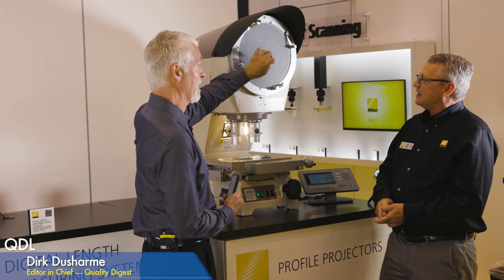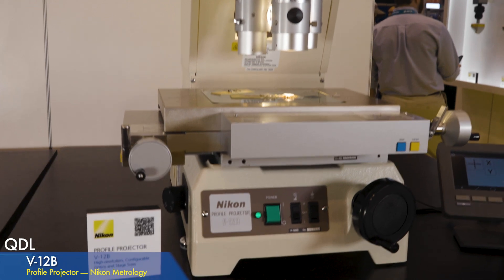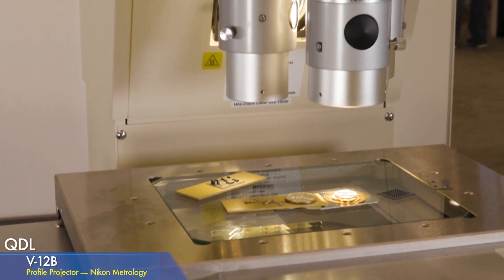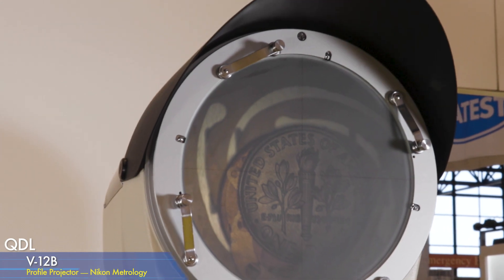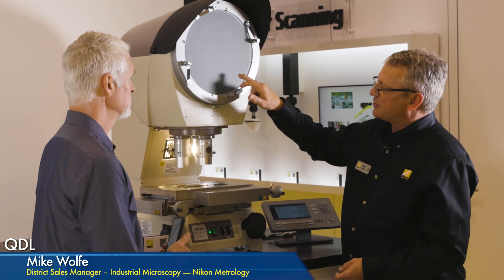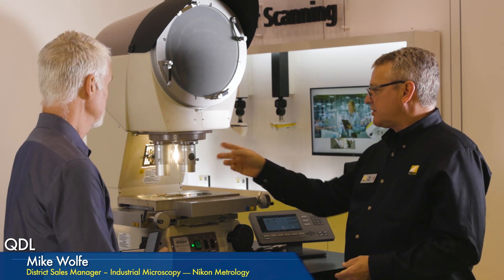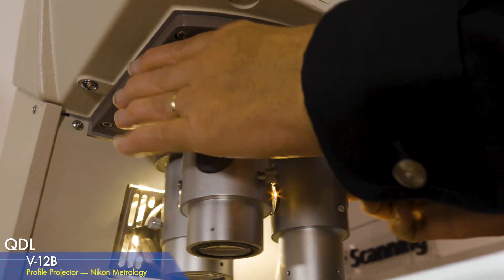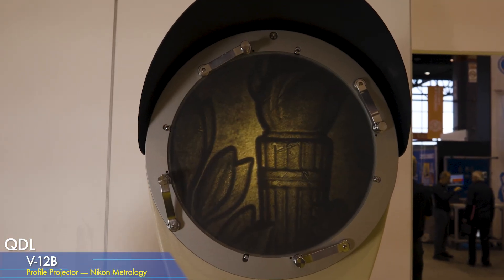This allows you to make measurements directly on the surface as opposed to just the outside edge. Most comparators bring light in shadow mode from beneath — you'd see a dark silhouette and just the edge. Because we have such good optics, we can show you an amazing reflected light image and pick out features on the surface to measure. This microscope can go up to 500x — it's the only comparator in the world that can accept a 500x lens. It has a three-lens turret so we can bring a variety of lenses into the field.